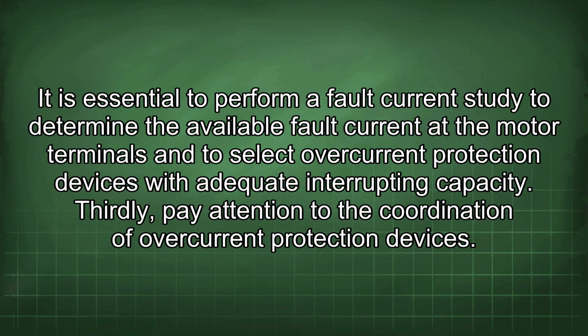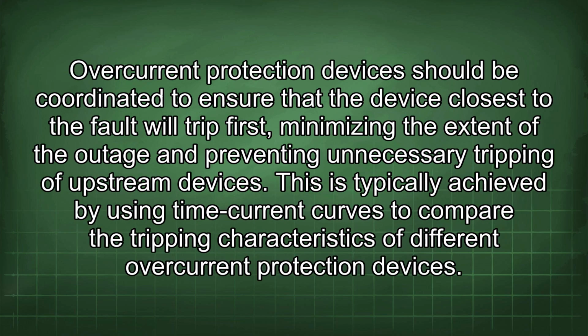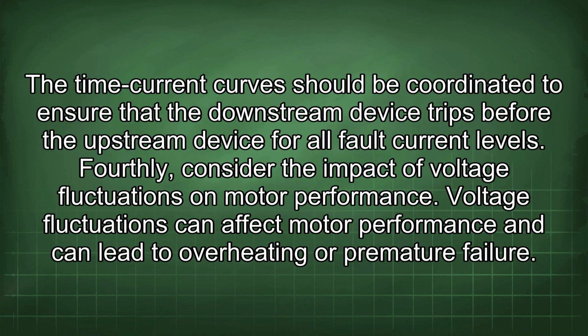Thirdly, pay attention to the coordination of overcurrent protection devices. Overcurrent protection devices should be coordinated to ensure that the device closest to the fault will trip first, minimizing the extent of the outage and preventing unnecessary tripping of upstream devices. This is typically achieved by using time current curves to compare the tripping characteristics of different overcurrent protection devices. The time current curve should be coordinated to ensure that the downstream device trips before the upstream device for all fault current levels.